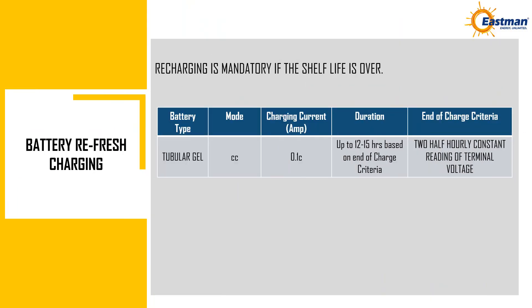Battery refresh charging. Recharging is mandatory if the shelf life is exceeded. Tubular gel batteries use CC (constant current) mode with 0.1C charging current in amperes, for 12 to 15 hours depending on end-of-charge criteria. End-of-charge criteria is defined as two half-hourly constant readings of terminal voltage.